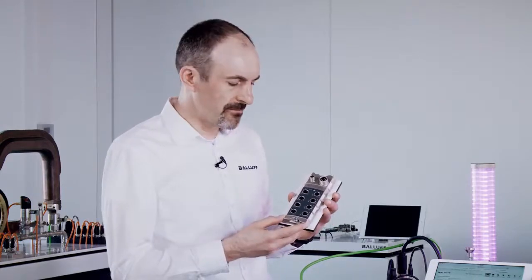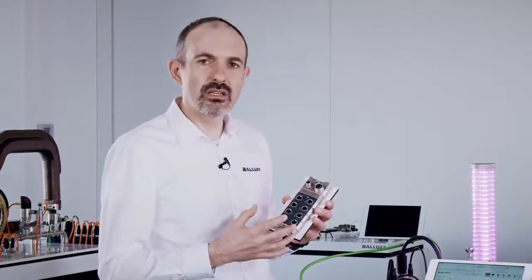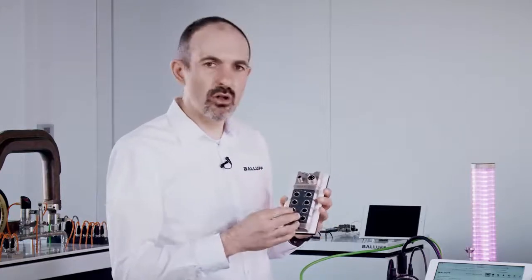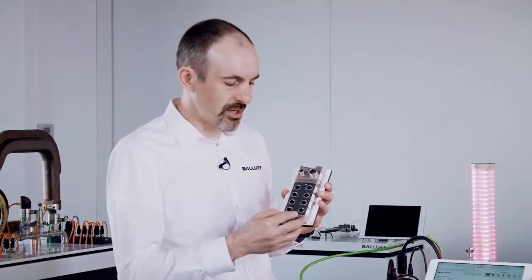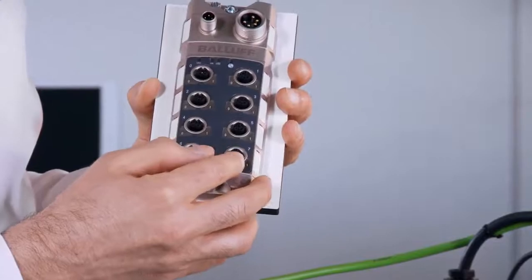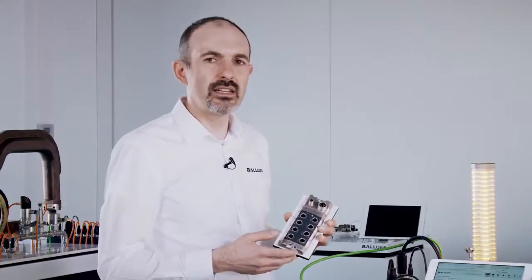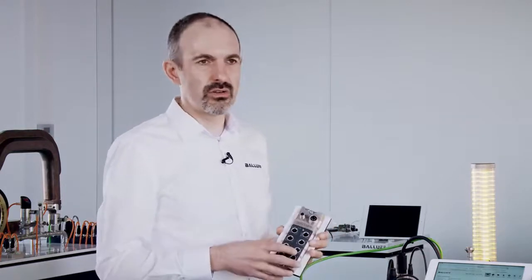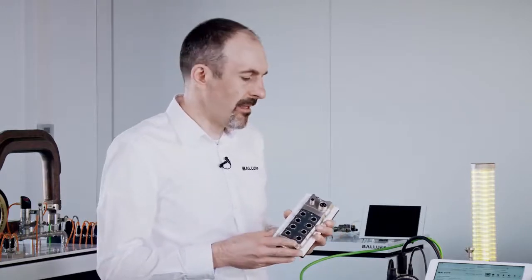In any case, if you have a short circuit, for example, it does not interrupt your whole machine or whole PLC. It only affects one port. You have clear diagnostic information on such a port with a red LED displayed here. So your maintenance person doesn't spend time finding a simple break caused by a short circuit, which is quite a common mistake on machines.